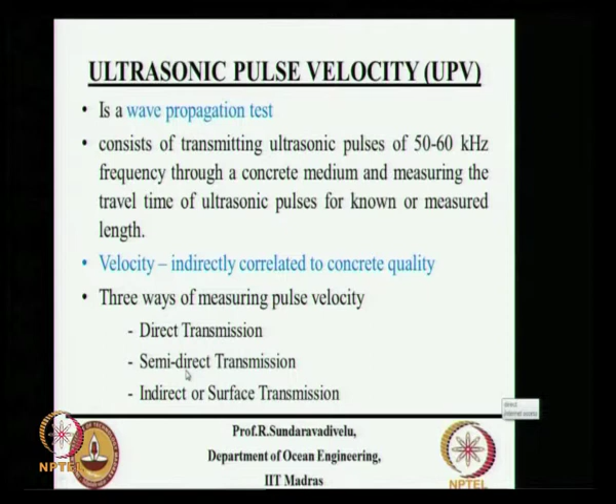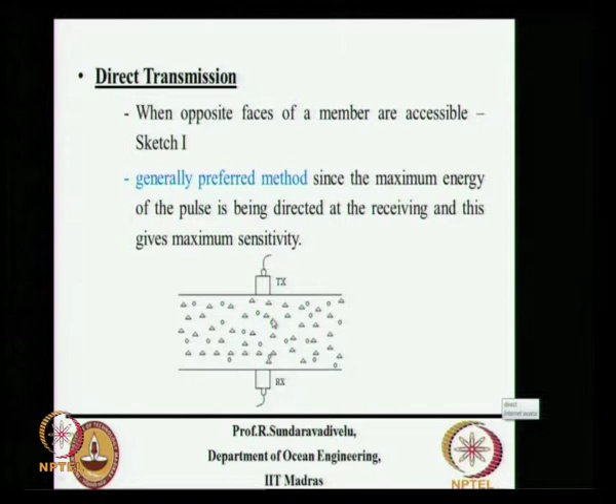You know the thickness and find out. So this is possible when opposite faces of a member are accessible. If you have accessibility on both the faces, then you can do it. This is the most preferred method, because the maximum energy of the pulse is directed at the receiving end, and this gives maximum sensitivity. Whenever you use the instrument, the sensitivity is important. The signal should not have any noise, and it should have sufficient amplitude to measure.